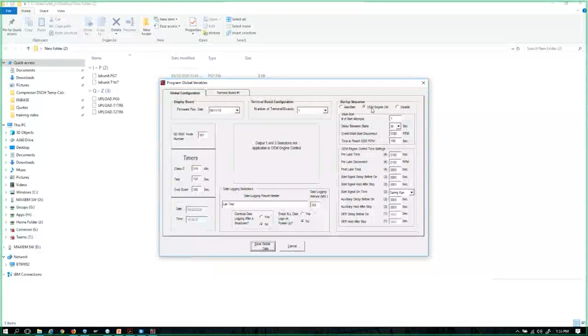But on the OEM start configuration, it locks the system up for safety. It will go into timers active, but it will never read auto start across the screen of the display, and none of the output modules on the power supply will illuminate or be energized. The only way to get it out of that lockup state is to push manual stop and then return and use a remote switch that's usually located on the front of the panel to trigger or excite the remote reset terminal.